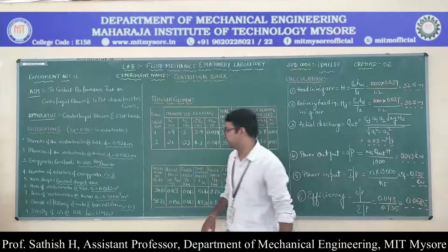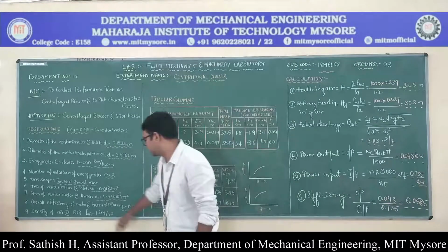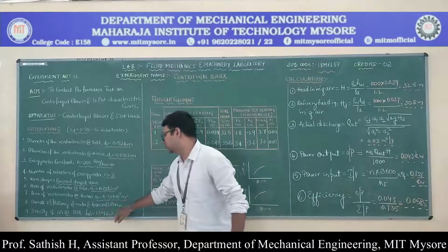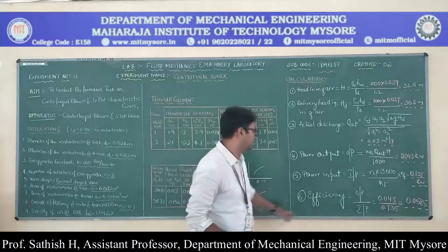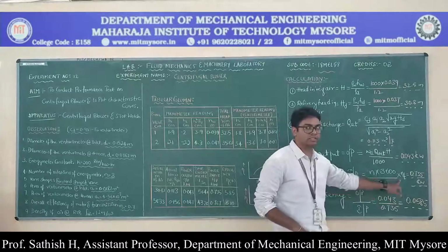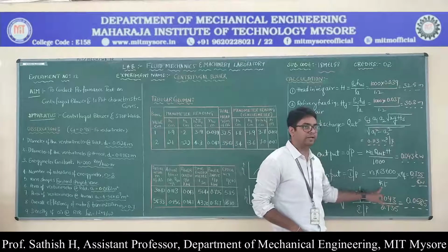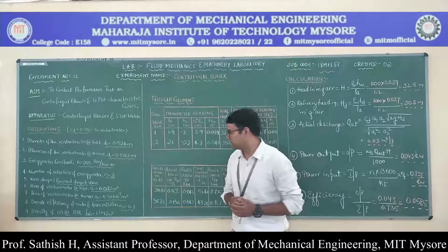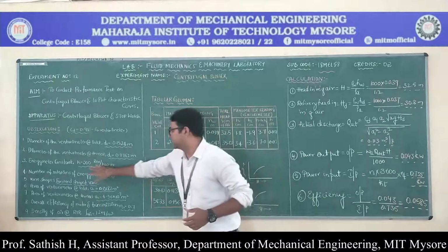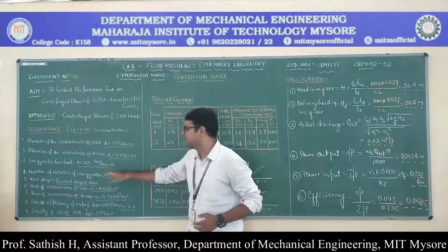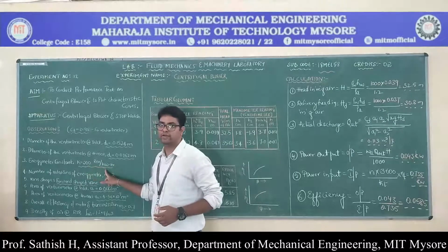What do we mean by eta T here? This is the overall efficiency of the motor and the transmission, that is 0.7, which you have to substitute, and then K times T, where K is the energy meter constant. If you look at the observation here, the energy meter constant is given as 200 revolutions per kilowatt hour.